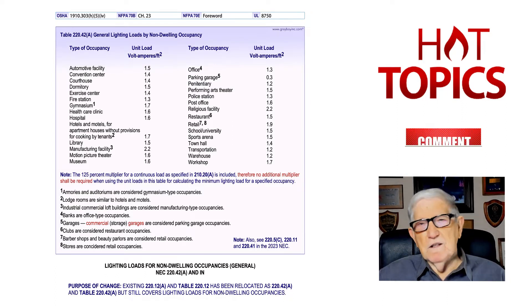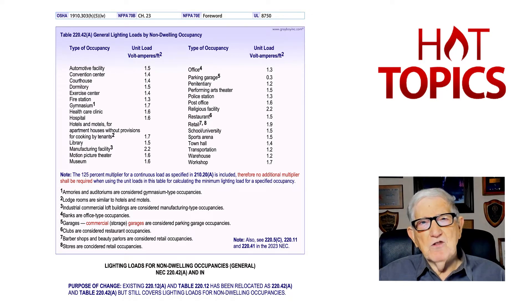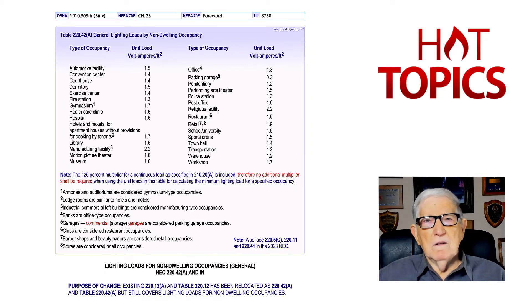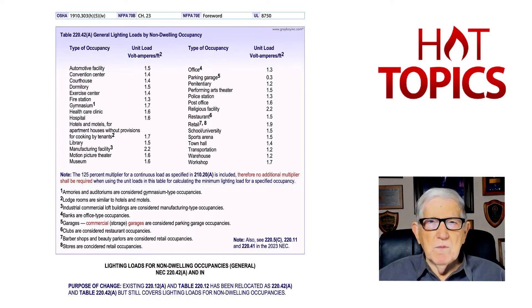If we go over and take a look at 210.20a on page 84 of the 2023 edition of the NEC, it'll be on the right-hand side of the page. It deals with the overcurrent protection device, and it says the continuous load at 125% plus the non-continuous load. Basically, if we took one and divided by 125%, that comes out to 80% — a derating of the breaker. So if you had a circuit breaker rated at 20 amps, 80% of that would be 16 amps, or take 16 amps at 125% and that would be 20 amps.